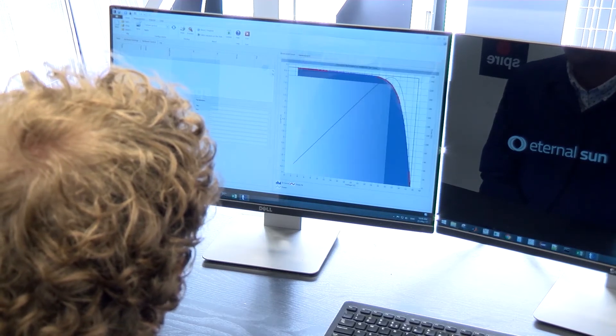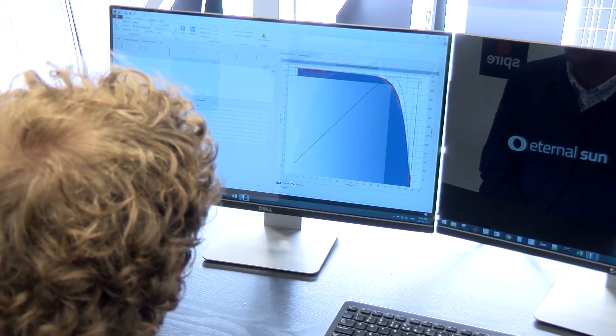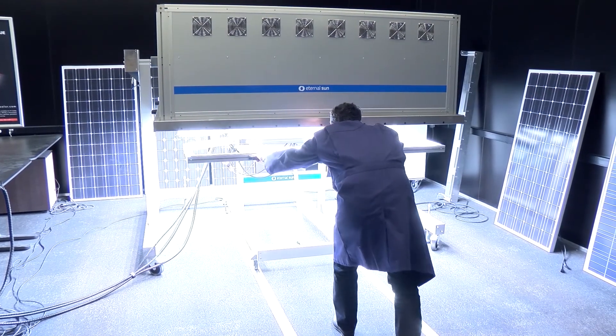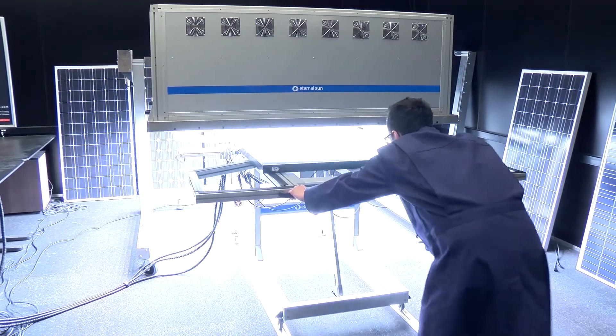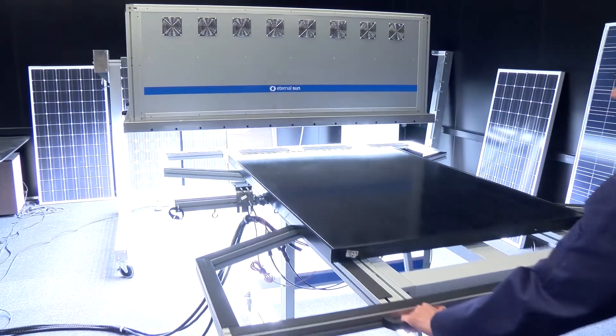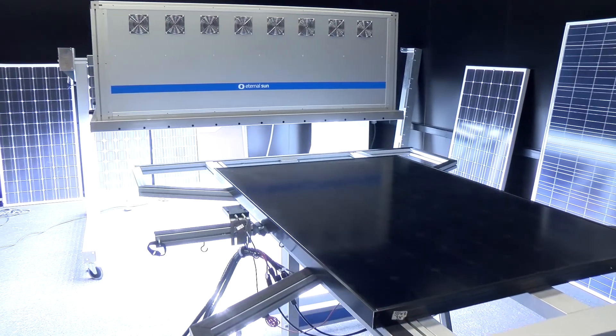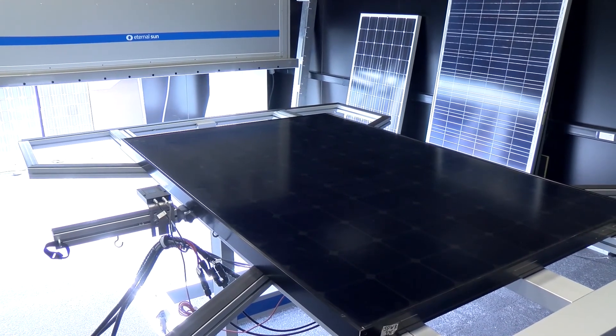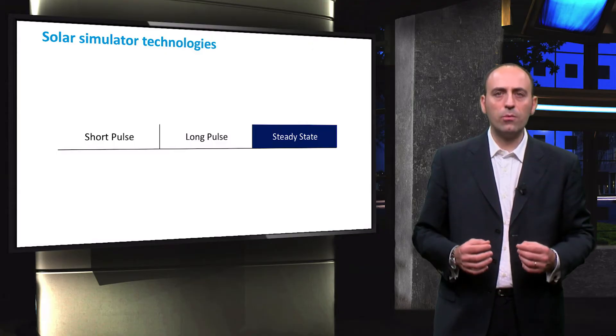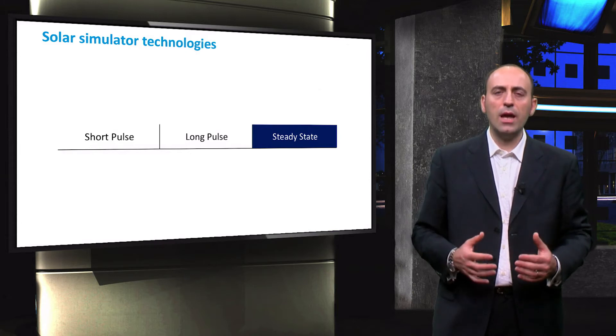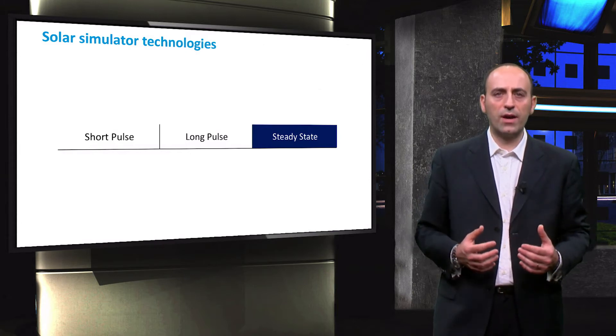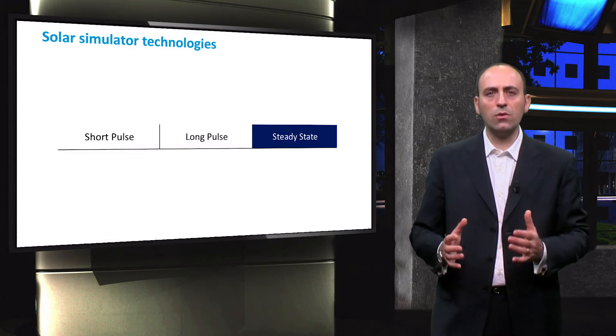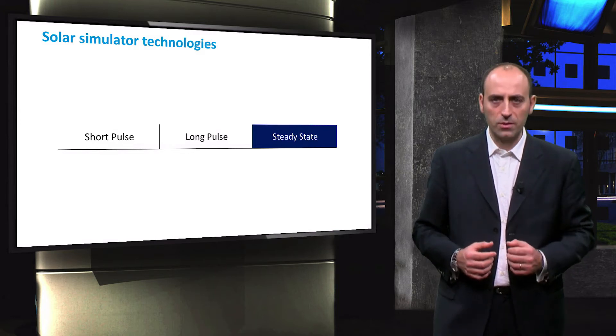This type of solar simulator can accomplish different tasks because its illumination is continuous in time. Unlike the previously explained technologies, the latter can also be used for power stabilization measurements, degradation measurements and light soaking, which is very important because light exposure can produce a variety of effects that influence the determination of both initial and long-term stabilized device performance.